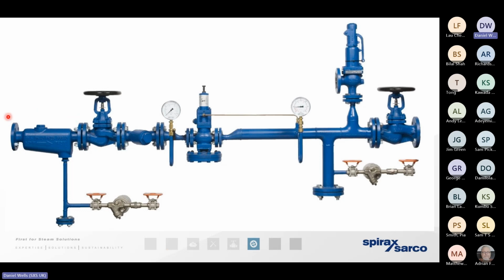So if we've got the steam coming in at the far left-hand side of the screen, the first thing we do is we remove any entrained moisture across that separator. That moisture condenses and we take it away across the steam trap. We've then got what we call an isolation valve, either end of the pressure reducing station, so we can isolate for basic maintenance, but we need to isolate it in order to commission it as well. Pipe strainer with its basket on the horizontal, so we're not trapping any condensate, but we're removing that particulate.